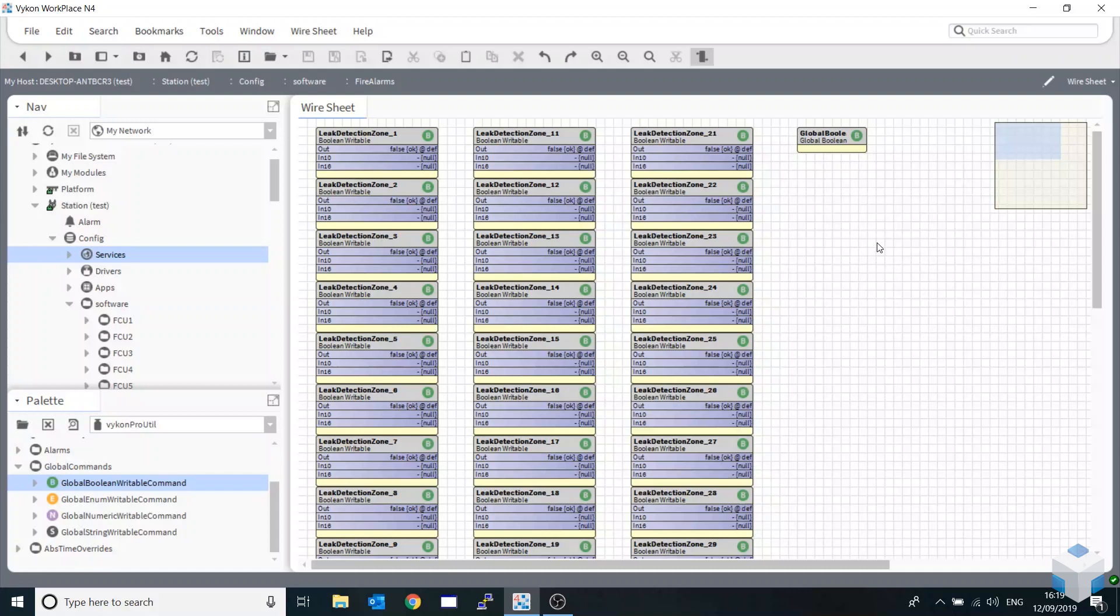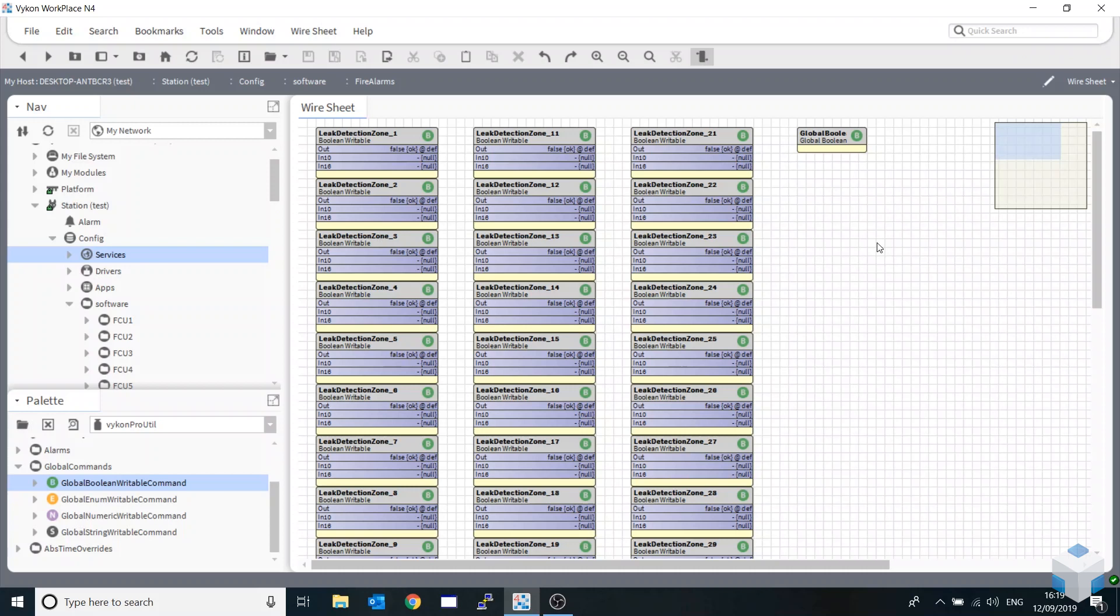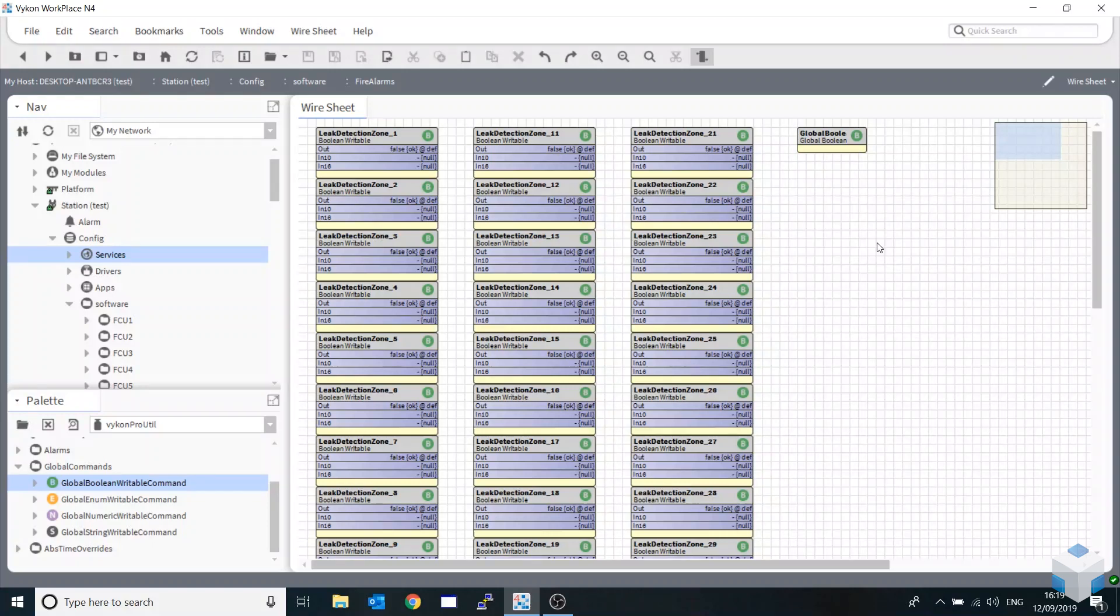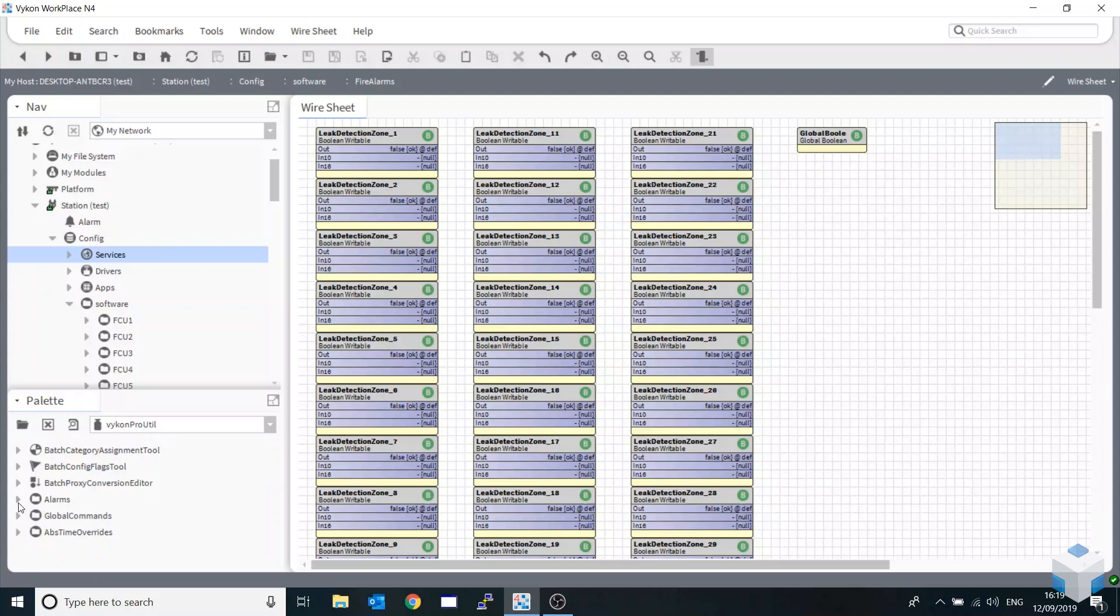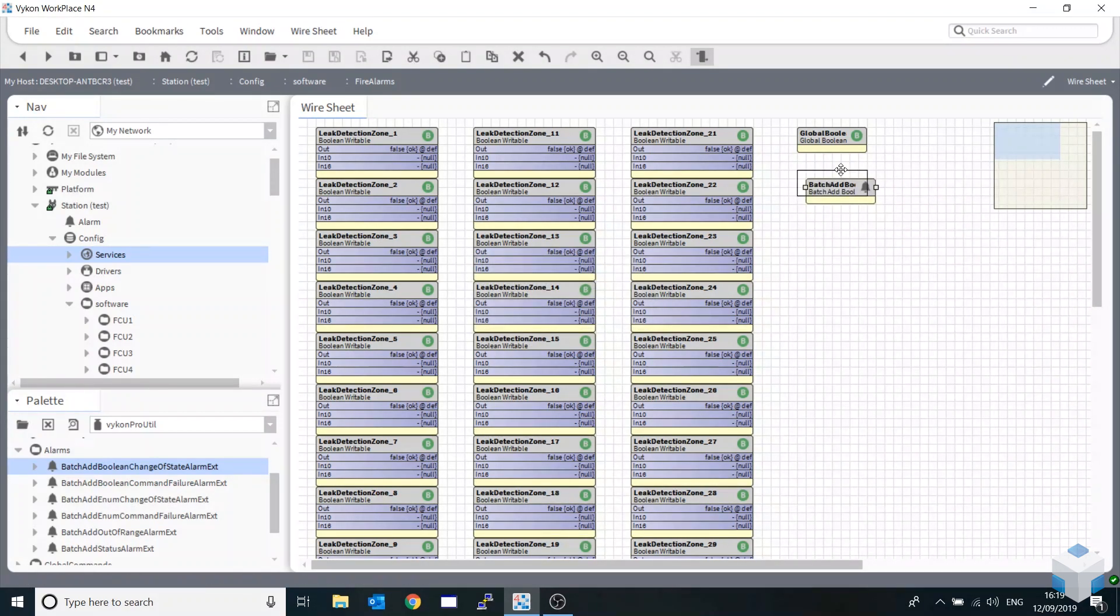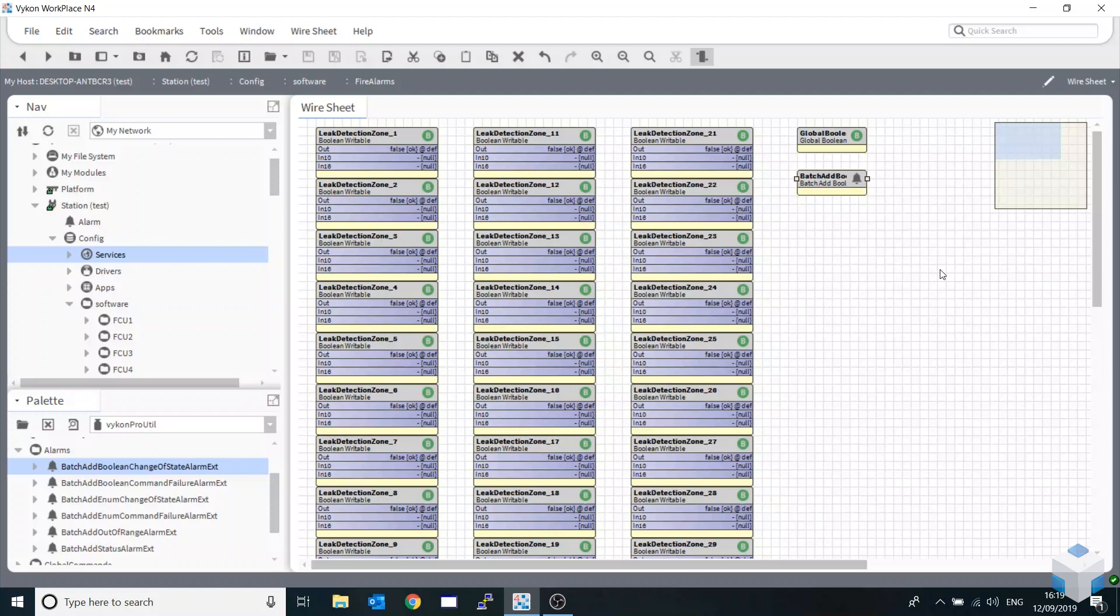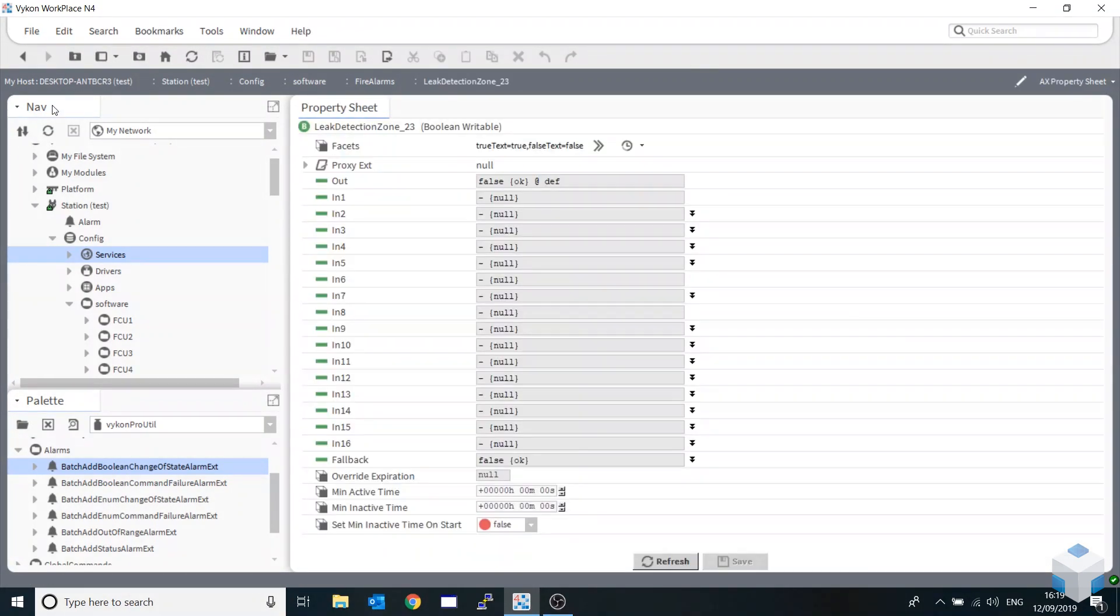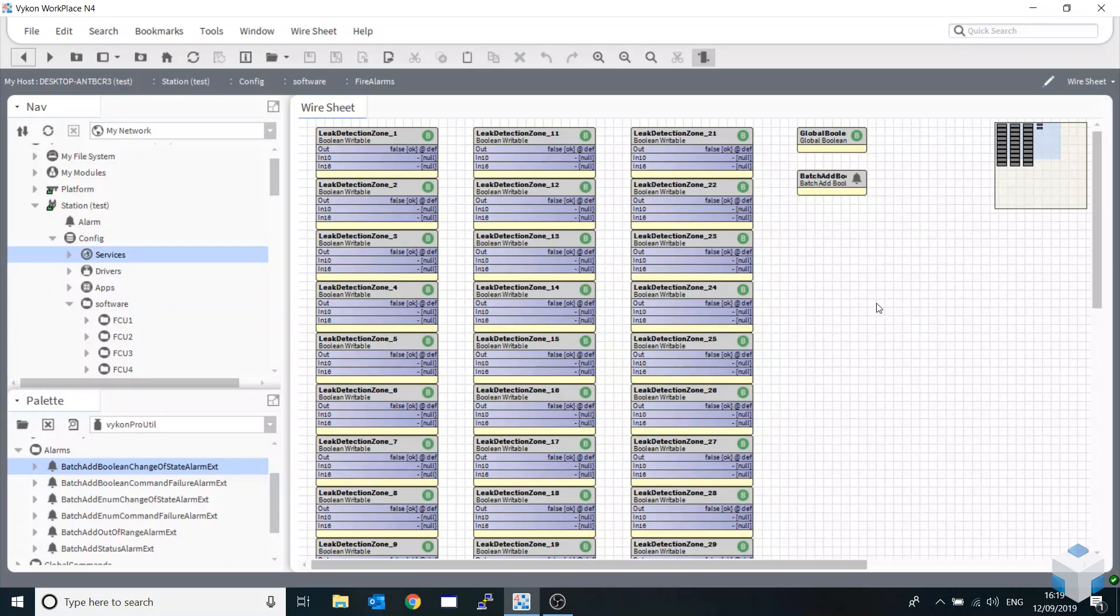Welcome back to the second part of our video on mass deployment. We'll be looking at how to add alarms on mass across our whole station. You might find that you've done a project and accidentally forgot to put an alarm extension, or the client has decided that he would like another extension added to your blocks on your station. I'm going to go back down to our Vykon Pro utility module, minimize the global commands, and bring out the alarm. I'm going to do a batch add boolean change of state alarm.